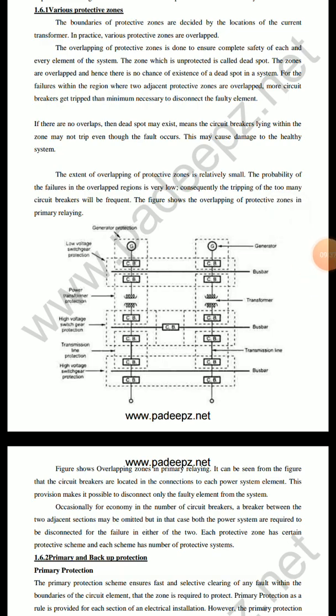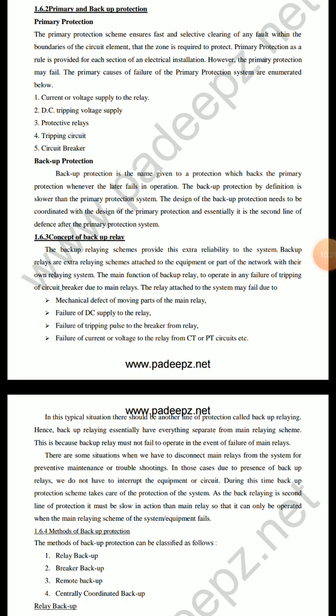And here are the various protective zones. Every dotted box is a separate zone: maybe the first one is generator protection, then bus bar protection, and transformer protection, either step-down or step-up type. These are the various selective zones. Two or more individual zones may be connected as one longer zone that we need to protect. These are the selective areas, and this is an important 8-mark question frequently asked in past university exams. Here we need to provide primary and backup protection.